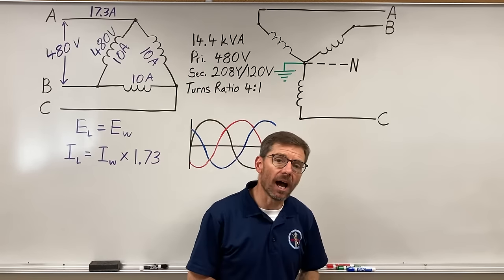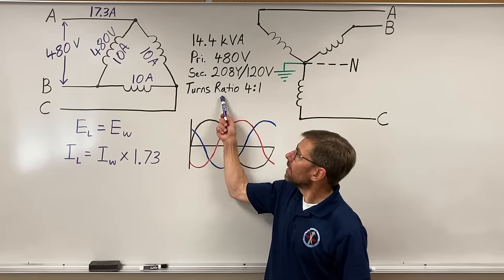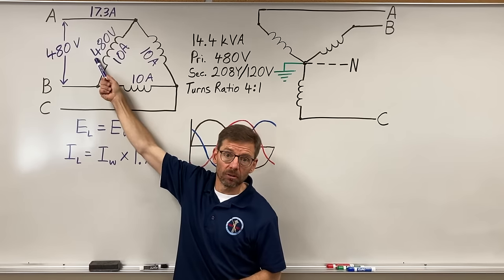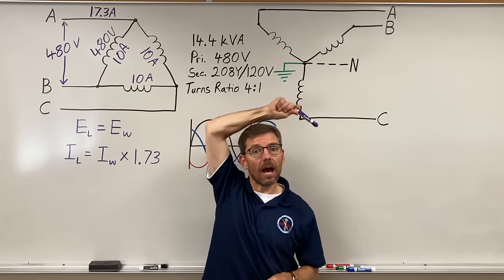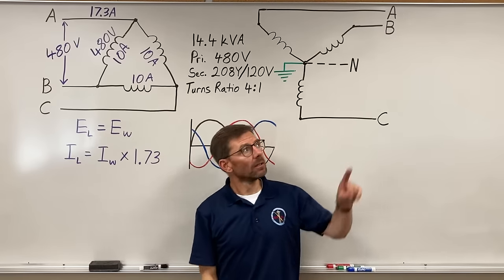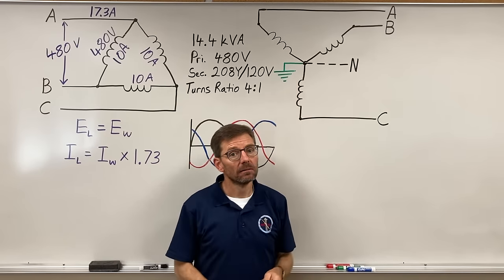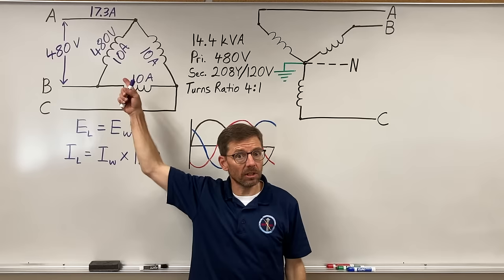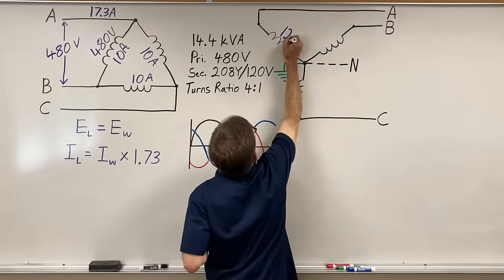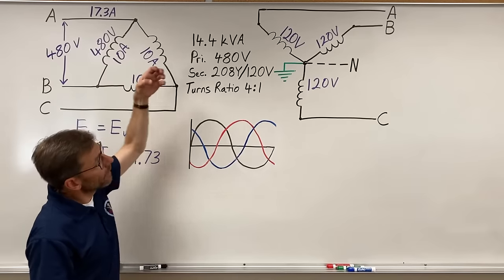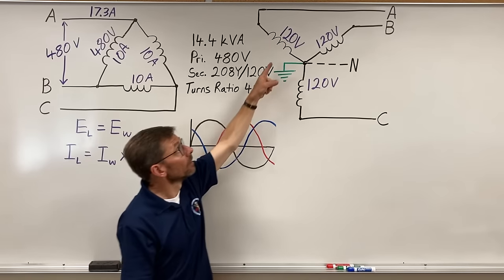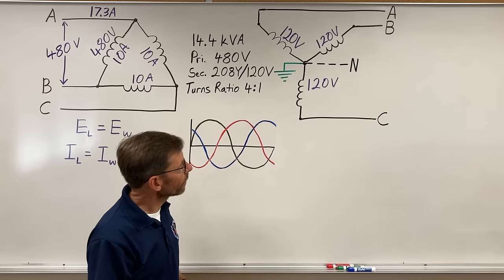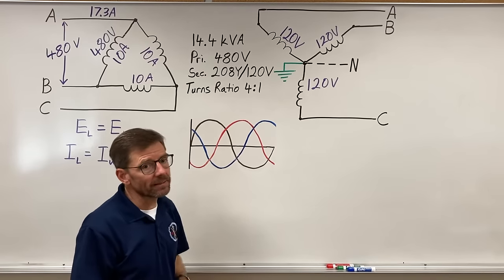Let's take a look over here at the Y. If my turns ratio is 4 to 1, that means this 480 volts has to step down. Four turns here for every turn here. The voltage here will be one quarter of the voltage here on each winding. So each winding is mutually inducing 120 volts into its respective secondary.